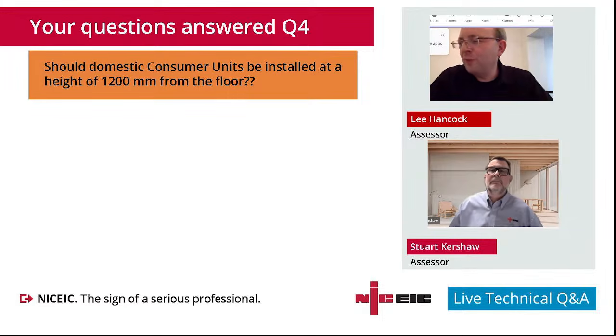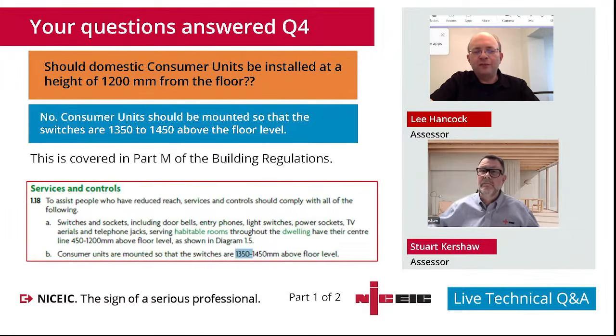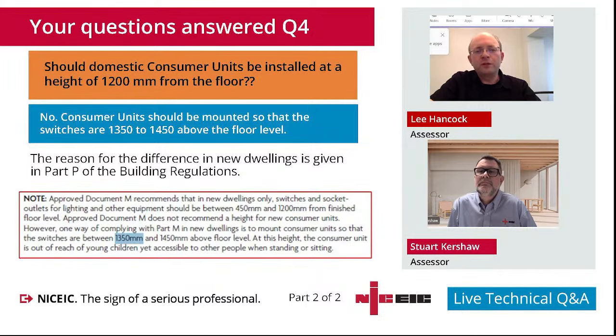Yeah. So Part M of the building regulations, accessibility, is what we're going to consider now, Sam. 1,200, no. The consumer unit is to the level of the switches, that is, 1350 to 1450. Any contractors wanting guidance on this, I know Stu's just plugged the pocket guides there, which I do quite regularly on site visits. Pocket Guide number 5 gives us recommended heights of switches, socket outlets and consumer units. It's worth adding though that if we're doing a rewire, we don't have to adhere to that height because the property is pre-existing. It's recommended that we do ultimately, but in some situations we can't. So we're not actually breaking any regulations if we're doing a rewire in an older building, but certainly in a newer property, a self-build or a newly developed property, we should be looking at 1350 to 1450.